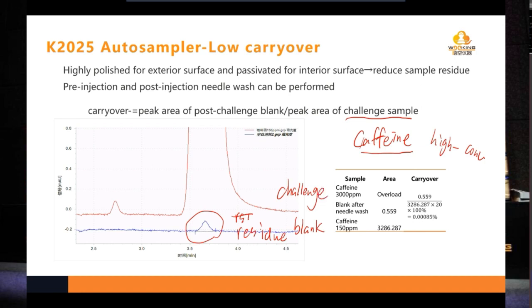The carryover is calculated by the ratio of the peak area of the blank sample to the challenge sample. The carryover is calculated as 0.00085% in this test. Actually, this value cannot be achieved for every sample and experiment. So we use 0.03% carryover as our spec.